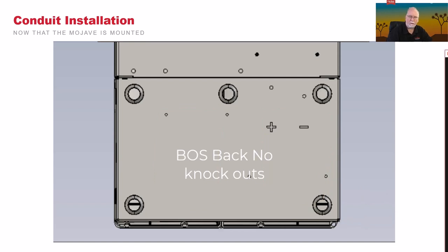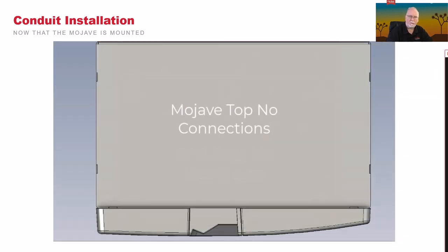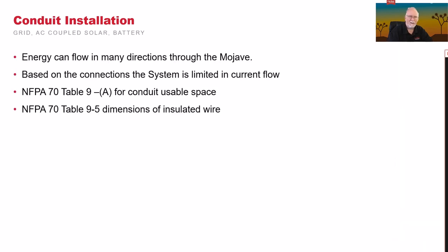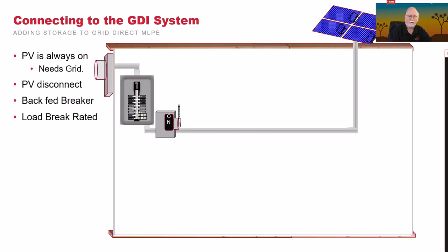Lastly, there is the top of the Mojave. The top of the Mojave will have no connections. You cannot run wires through the Mojave inverter section in order to connect it. That'll violate your warranty and UL as well. So important things to note is that energy can flow in many directions within Mojave. Based on the connection, the system will limit current flow, and use NFPA Table 9 for conduit usable space, and NFPA Tables 9-5 dimensions of insulated wire to help you in determining the wire and the size of the conduit you need for the installation.